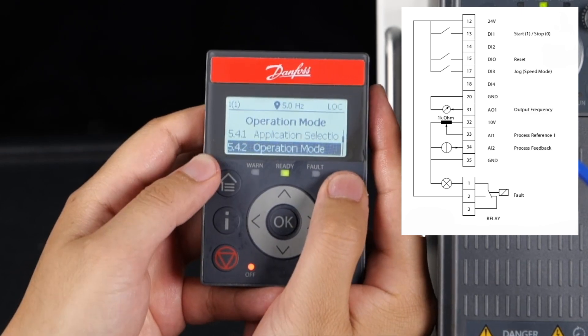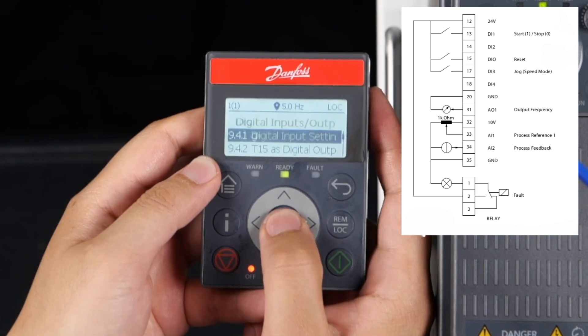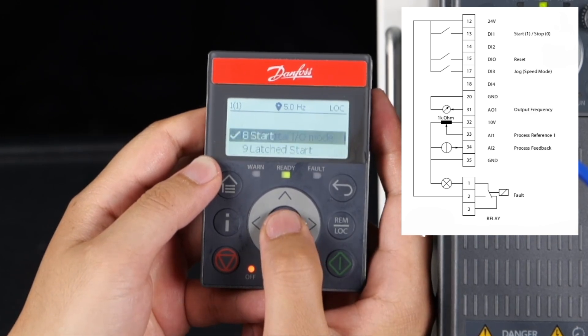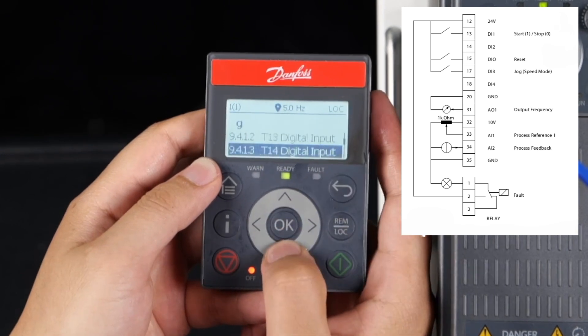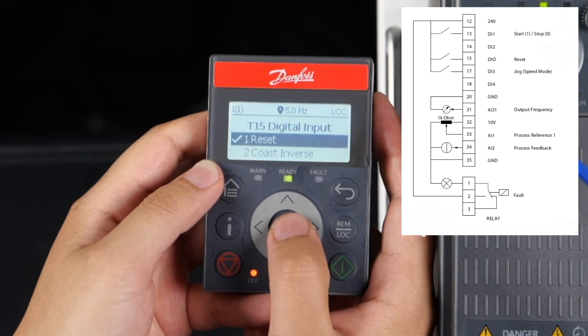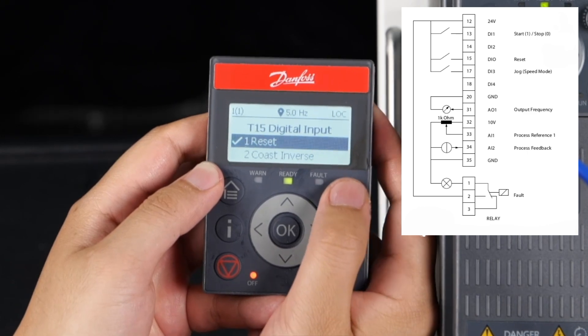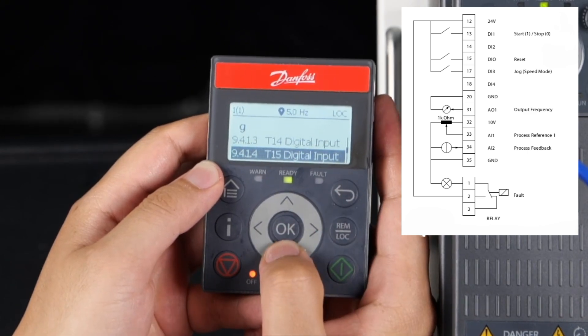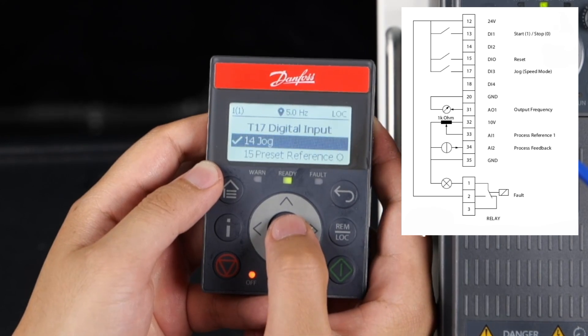Then set the relevant parameters for digital inputs. Set parameter 9412 — the default function of terminal 13 is 8: start. Set the parameter for terminal 15, and its default is 1: reset. Set parameter 9415 — the default function of terminal 17 is 14: jog.